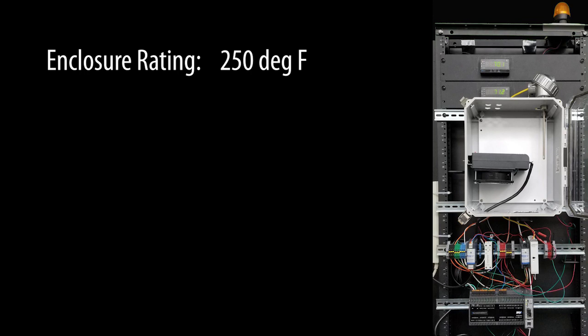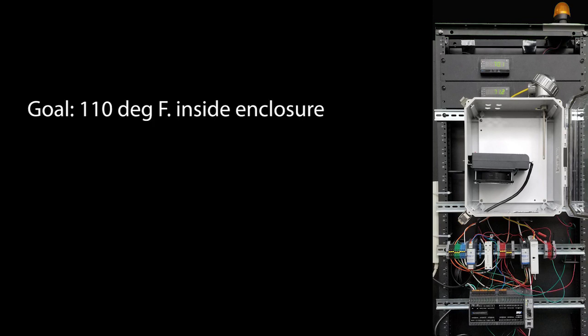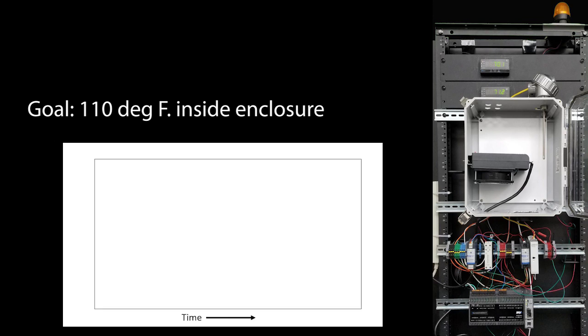Well, we want to maintain an accurate 110 degrees Fahrenheit inside the enclosure, right? And we want to give PID as much headroom as we can so it can do its job. That is, if you want to hold the temperature at 110 degrees, then it really helps PID to have the ability to go way past 110.